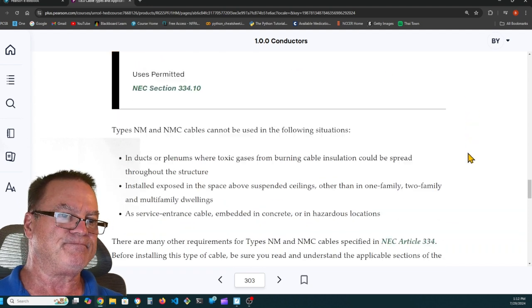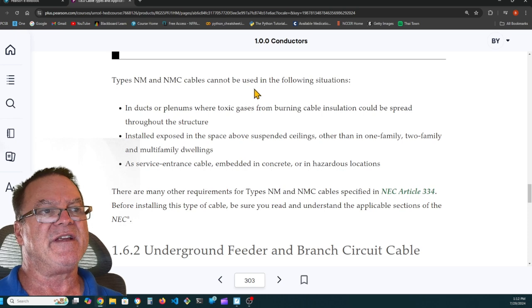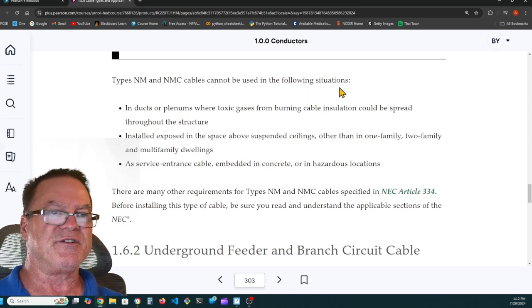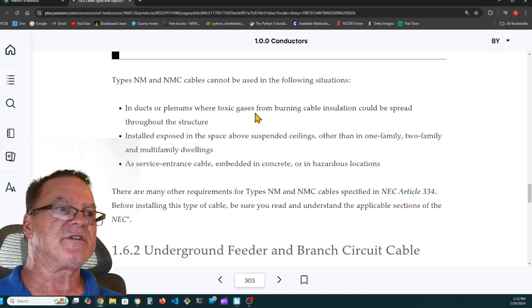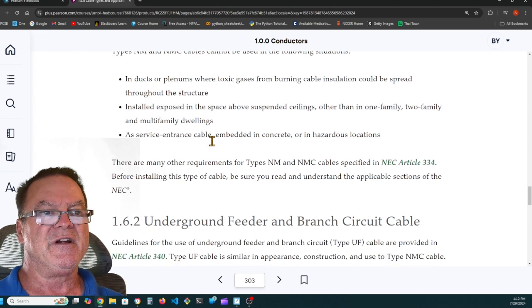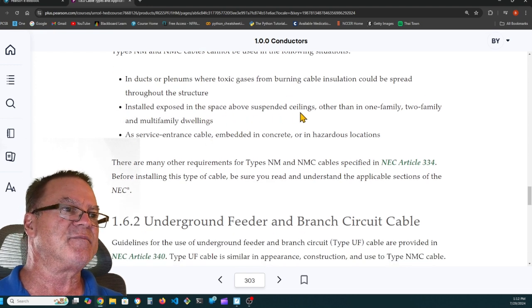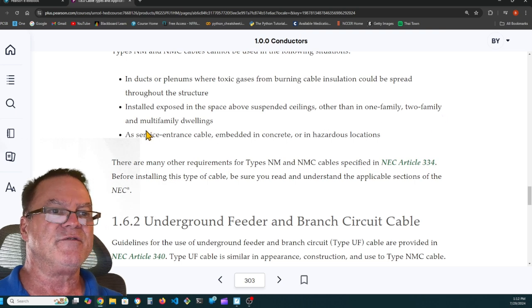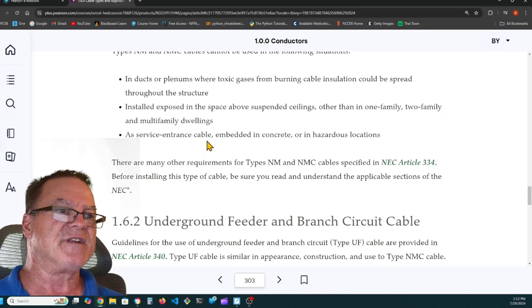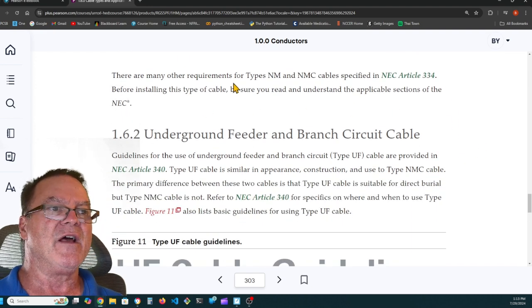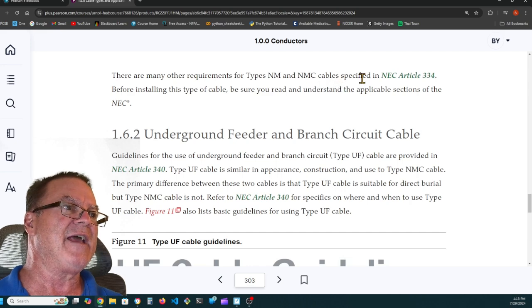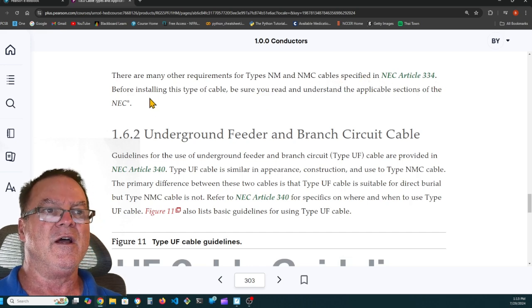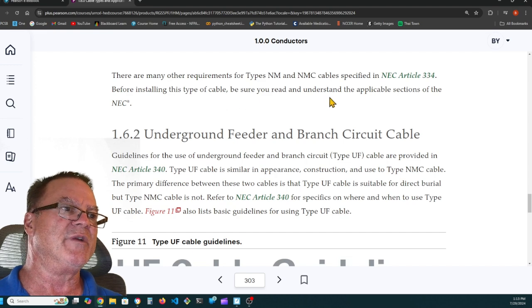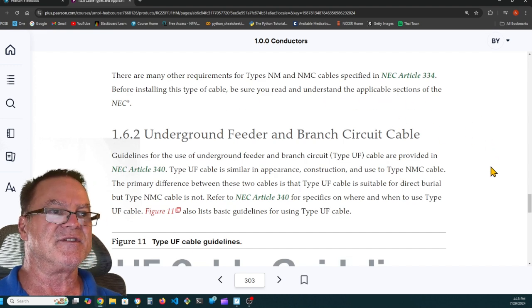type of construction. Type NM and NMC cables cannot be used in the following situations: in ducts or plenums where toxic gases from burning cable insulation could be spread throughout the structure, installed exposed in the space above suspended ceilings other than in one-family, two-family, and multifamily dwellings, as service entrance cable, embedded in concrete, or in hazardous locations. There are many other requirements for types NM and NMC cables specified in Article 334. Before installing this type of cable, be sure you read and understand the applicable sections of the NEC.